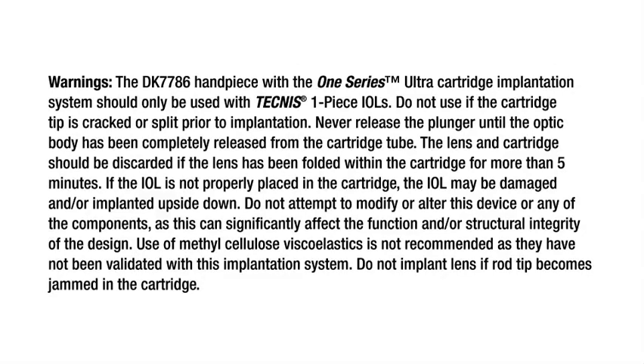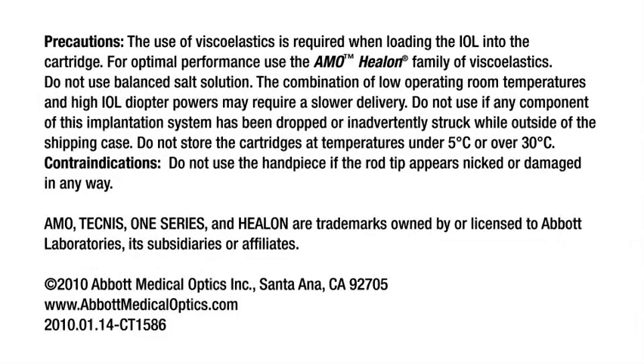Do not attempt to modify or alter this device or any of the components, as this can significantly affect the function and/or structural integrity of the design. Use of methylcellulose viscoelastics is not recommended, as they have not been validated with this implantation system. Do not implant the lens if the rod tip becomes jammed in the cartridge. The use of viscoelastics is required when loading the IOL into the cartridge. For optimal performance, use the AMO Healon family of viscoelastics.